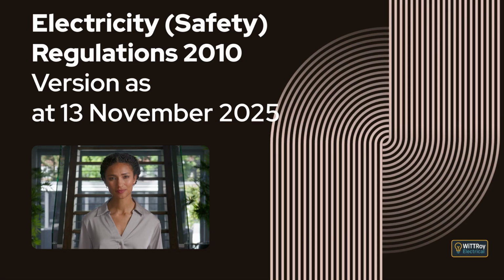The regulation then explains that a person carrying out the inspection must take whatever tests, visual checks, or other actions are necessary to be satisfied that the work has been done in accordance with the regulations, and that the installation or part installation is, and will be when energized, electrically safe. Reg 71 Who may carry out inspection.